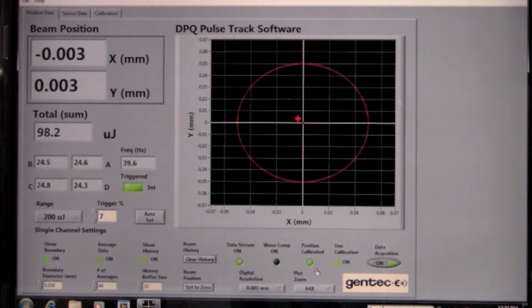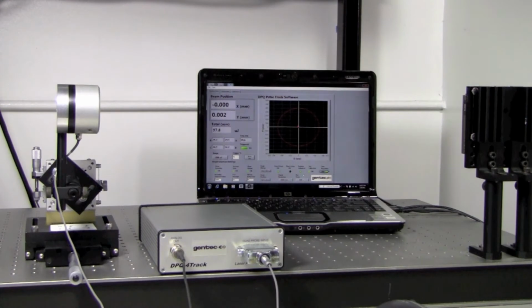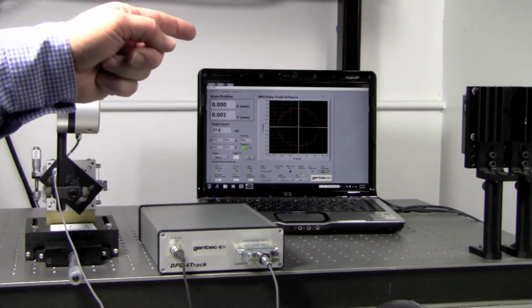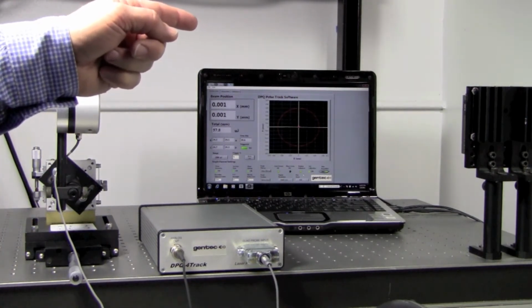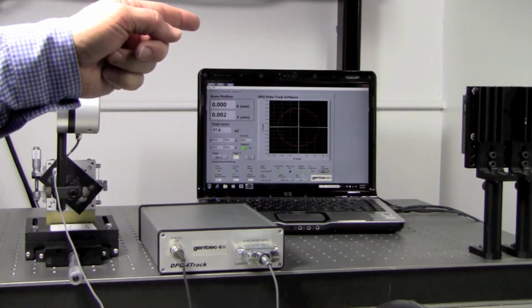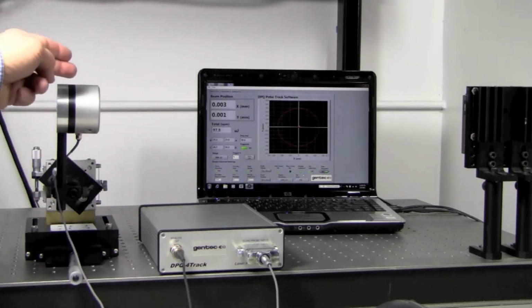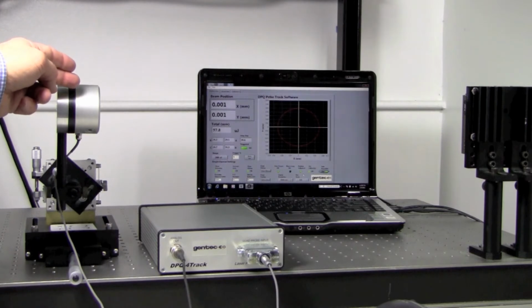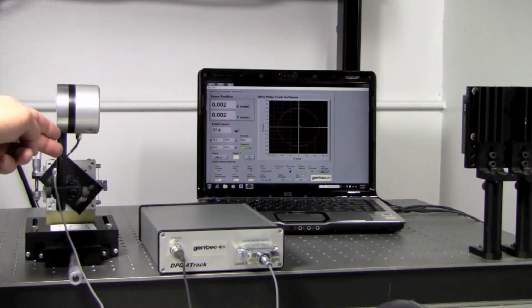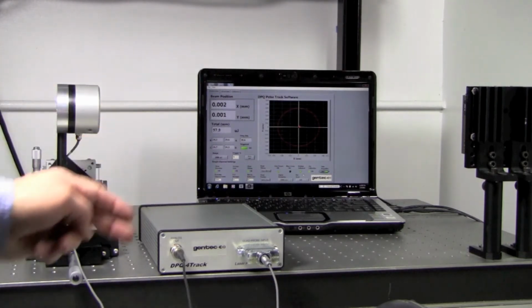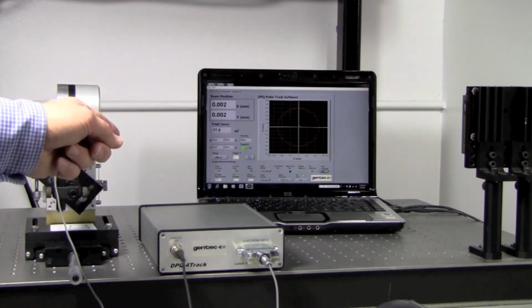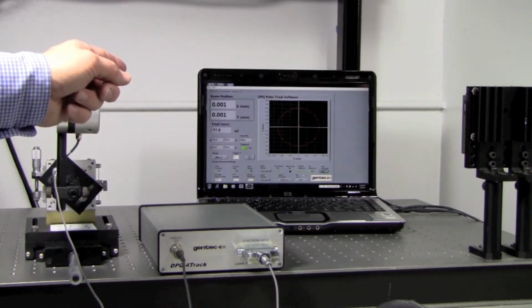Let's take a look at the DPQ4Track optical setup. We're measuring the beam position of a pulsed Q-switched YELF laser running at about 100 pps and with pulse energy of about 97 microjoules. This is our 9 mm quad joule meter probe set up on an XY stage. It's connected to our 4-track instrument. The USB output is connected to the computer running our 4-track software.